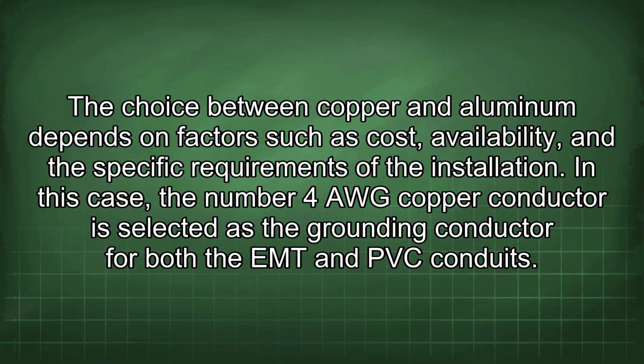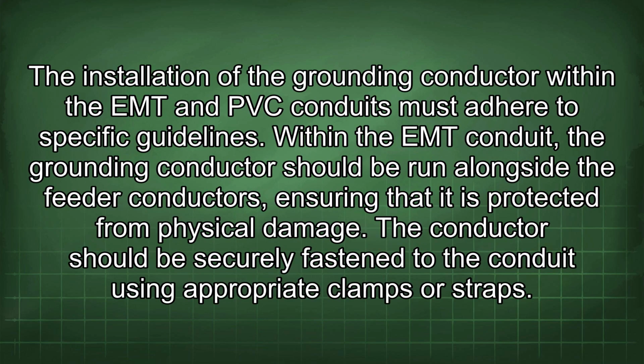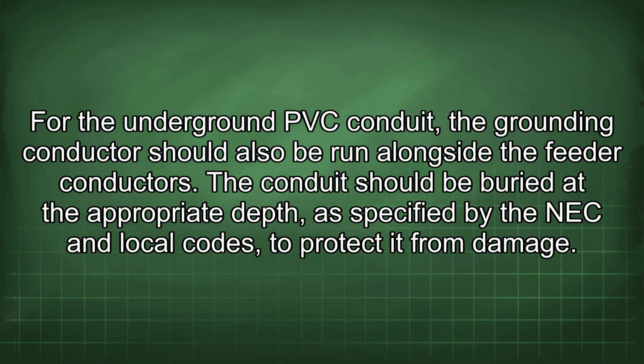In this case, the number 4 AWG copper conductor is selected as the grounding conductor for both the EMT and PVC conduits. The installation of the grounding conductor within the EMT and PVC conduits must adhere to specific guidelines. Within the EMT conduit, the grounding conductor should be run alongside the feeder conductors, ensuring that it is protected from physical damage. The conductor should be securely fastened to the conduit using appropriate clamps or straps. For the underground PVC conduit, the grounding conductor should also be run alongside the feeder conductors. The conduit should be buried at the appropriate depth, as specified by the NEC and local codes to protect it from damage.